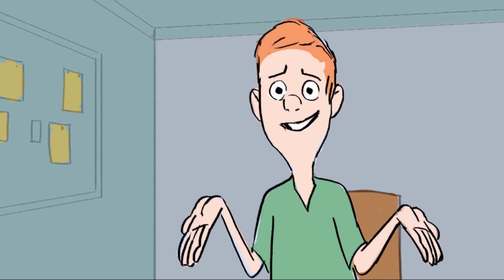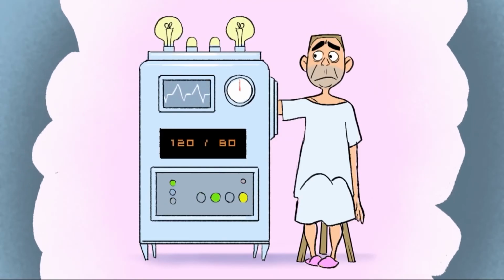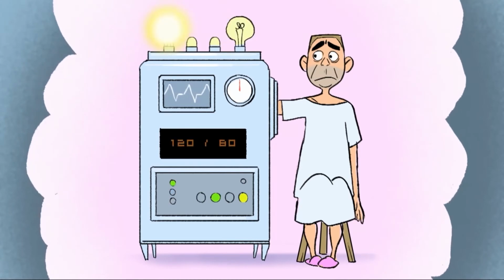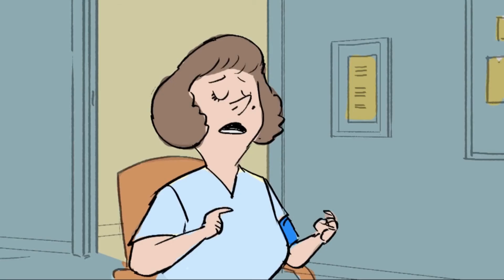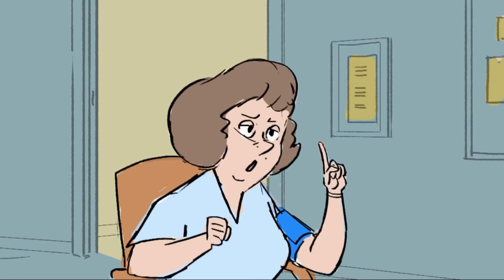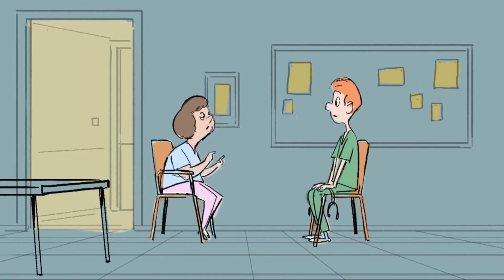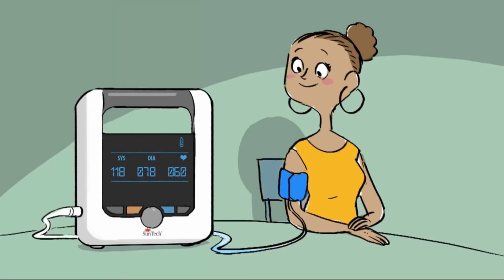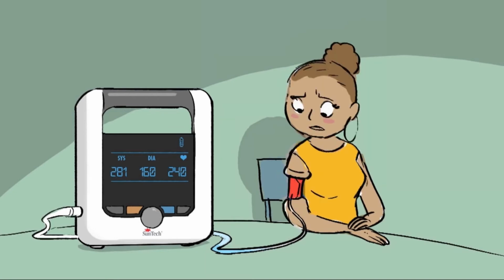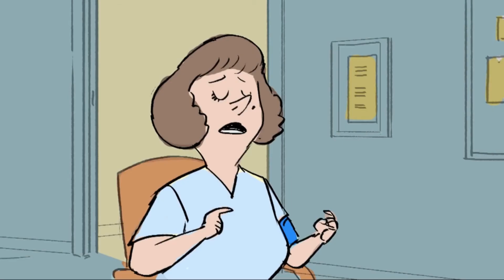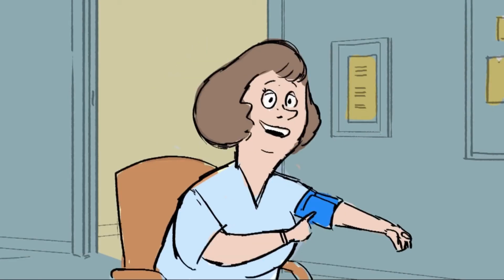I mean, this seems like a lot of trouble. Why don't we just use one of those newfangled automatic blood pressure machines? Since it's all automated, we don't really need to worry about sizing and artery placement and all that, right? Well, that's wrong. Correct cuff sizing and placement is even more important for automated devices than for old-fashioned manual ones. Really? Really. For modern automated machines, the cuff is extremely important. I want you to think of it as kind of a finely tuned, highly calibrated sensor. You use the wrong sensor, you get the wrong reading. Oh, I see. Now show me how to put the cuff on the right way.